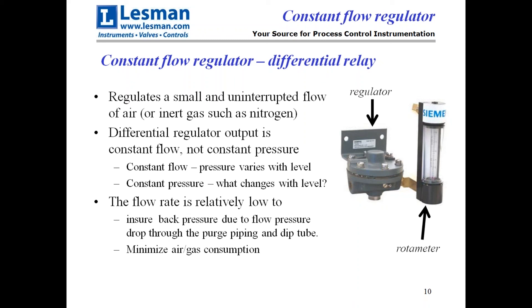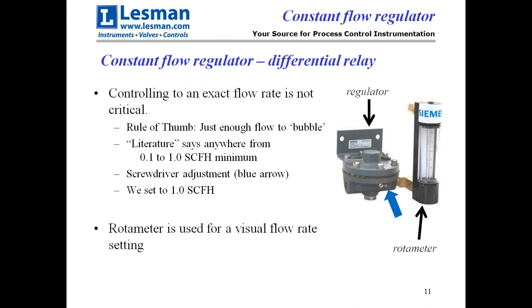The flow rate is relatively low, primarily because we don't want too much air flowing through the dip tube — which could cause pressure losses — and also to minimize air or gas consumption, since it costs money to compress air. The rule of thumb is you need just enough flow to bubble. Literature shows anything from 0.1 to 1 standard cubic foot per hour as a minimum. At the factory we set it to 1 SCFH, with a range up to about 2.5 to 3 on the rotometer — it's a visual indication that you still have flow running.